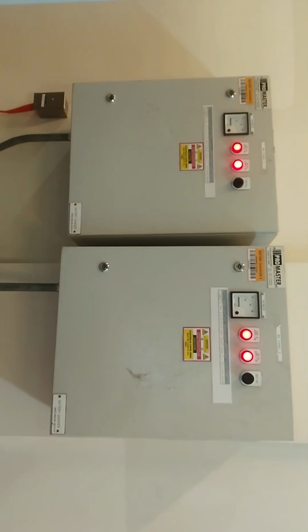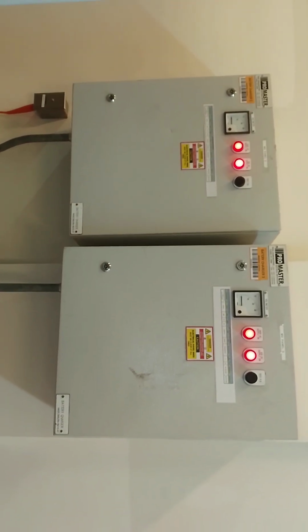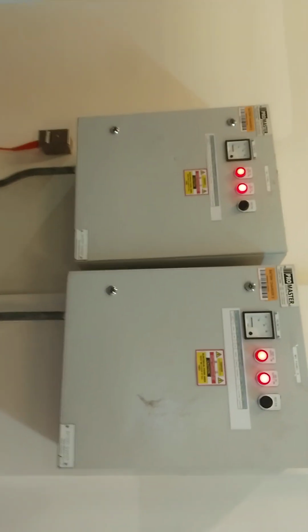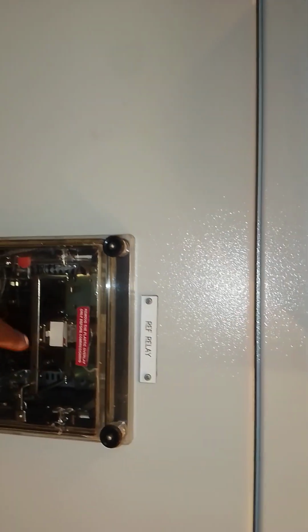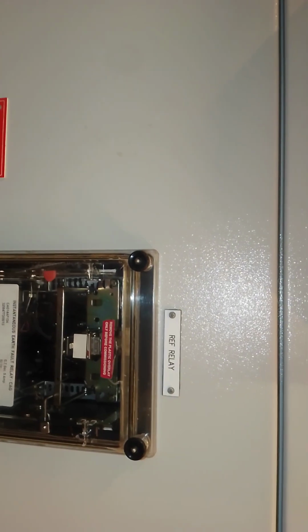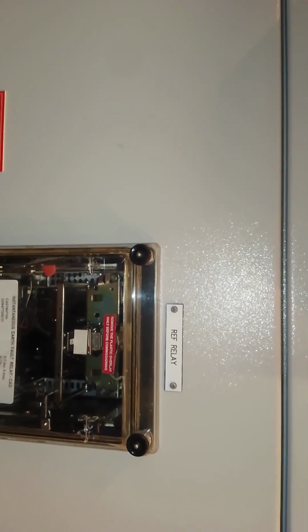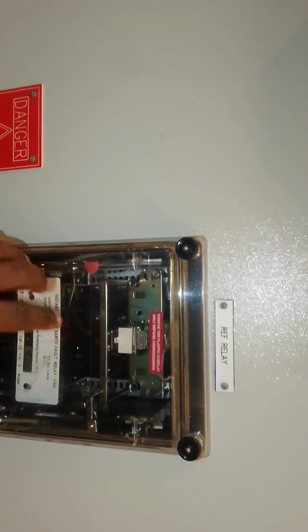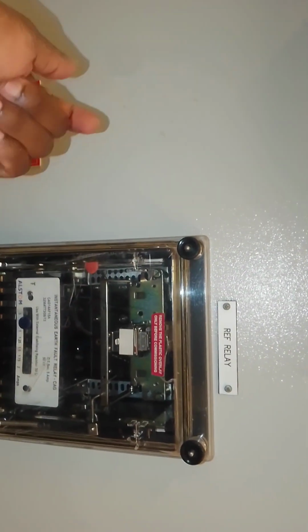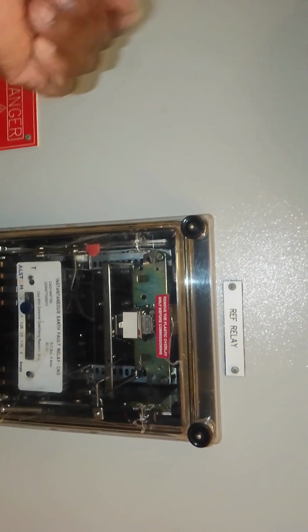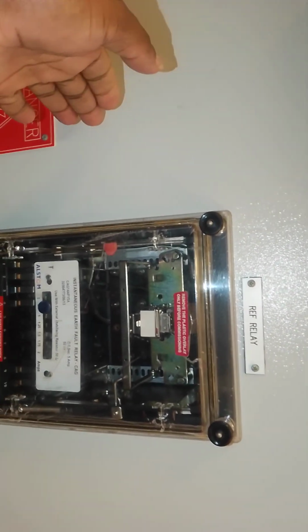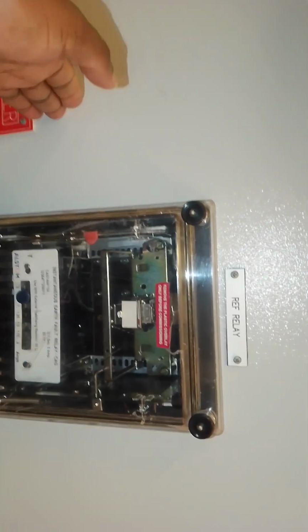We have these panels. This is our battery backup, and fed for this relay REF. When we have a earth fault, this one will automatically switch the system off, because it's already fed by the power from the batteries, and also is connected to the ACB.